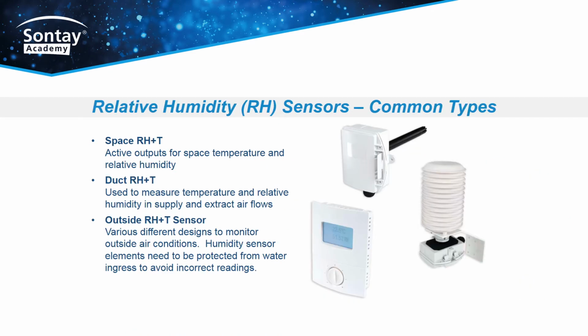Relative humidity sensors. Here are some common types. A space RH&T, which has active outputs for space temperature and relative humidity. Duct RH&T, which is used to measure temperature and relative humidity in supply and extract airflows. An outside RH&T sensor. Various different designs to monitor outside air conditions. Humidity sensor elements need to be protected from water ingress to avoid incorrect readings. They also are protected with a radiation shield in sunny positions.